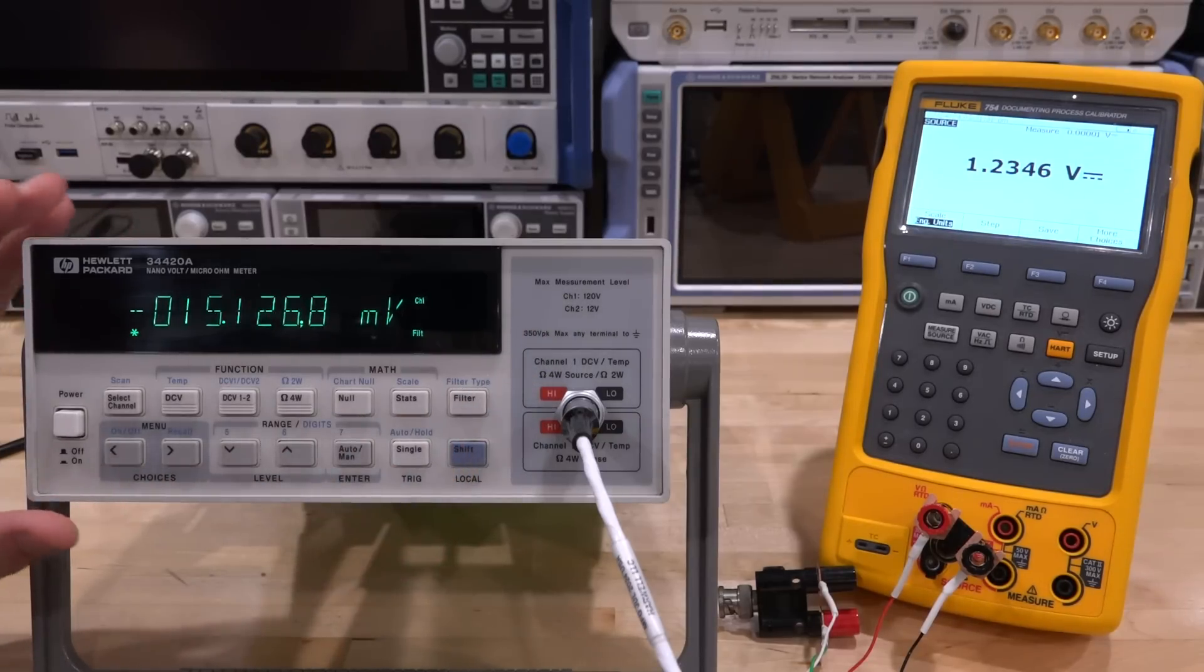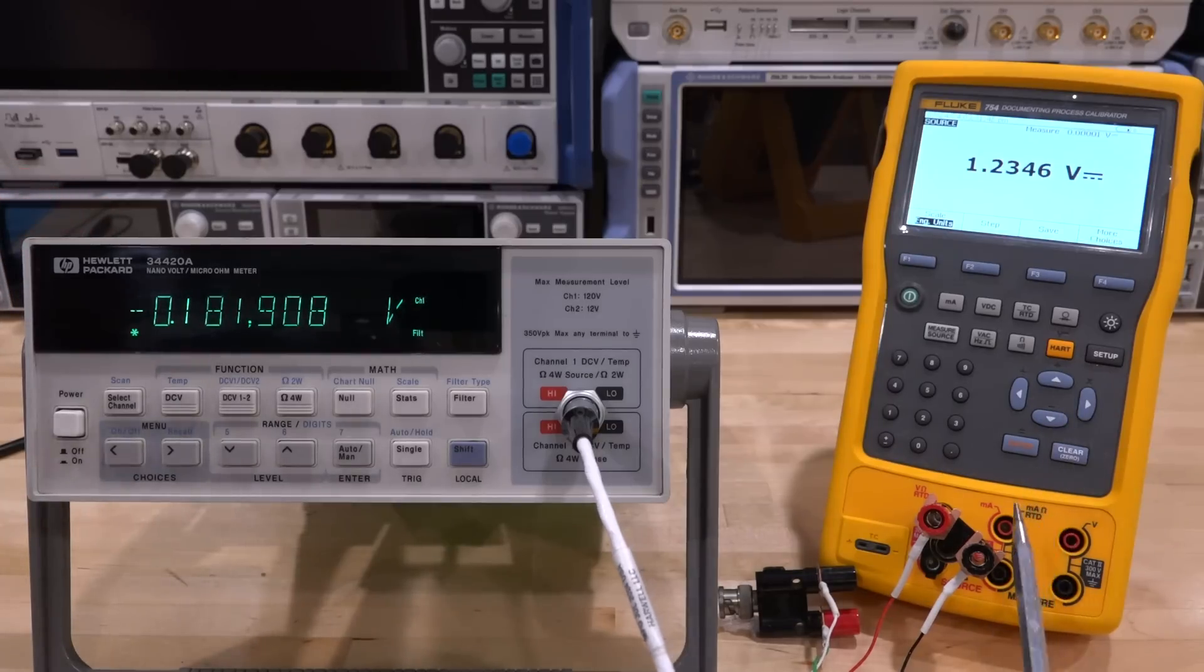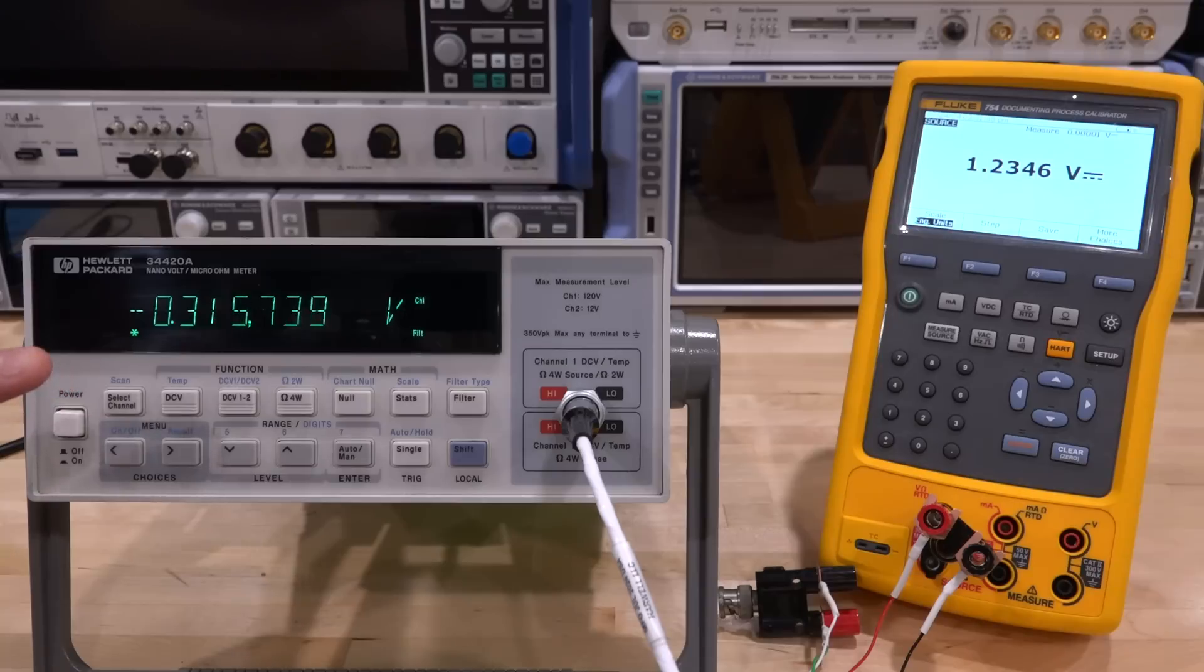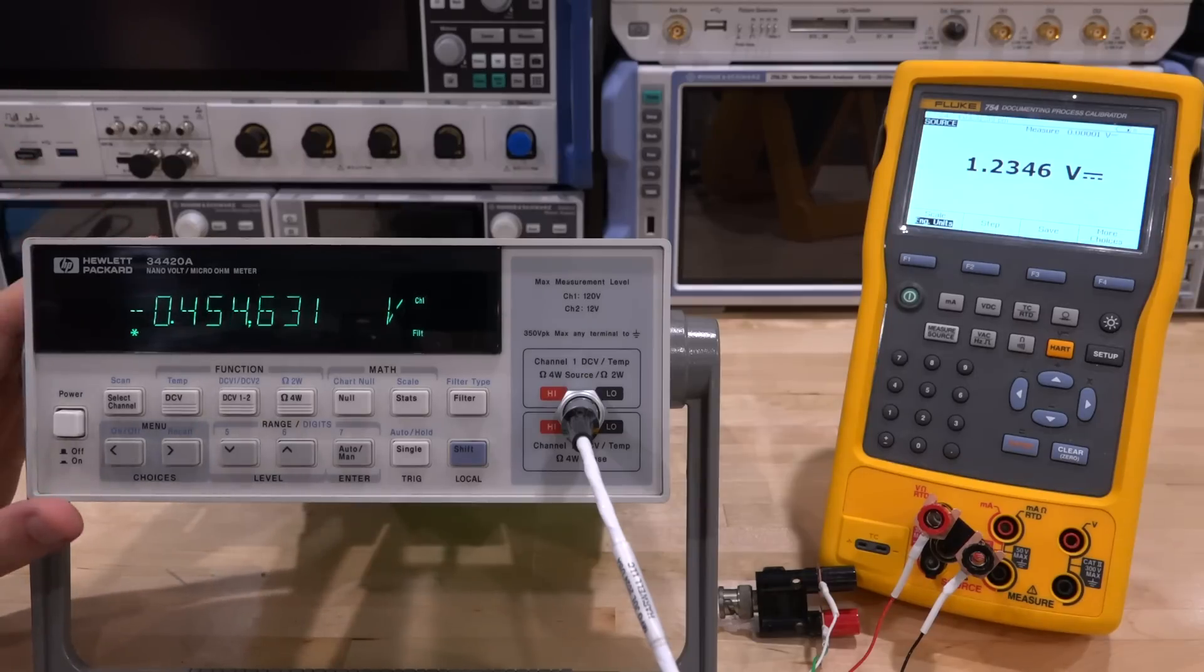Now the back end of all these instruments is the same. There's only one digitizer and one reference shared between the two channels, so it has to switch between them. Right now I have it set to channel 1, connected to the Fluke 754 documenting process calibrator. I'm applying 1.23456 volts but as you can see, I'm measuring nothing. Channel 1 is not responding at all, and that's what was wrong with it. I've always wanted one of these but they're quite expensive - this was almost $800 even when broken.